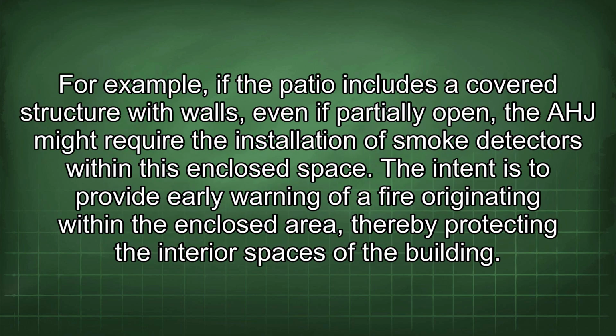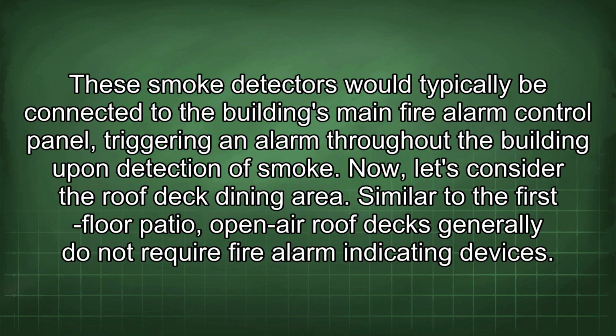For example, if the patio includes a covered structure with walls, even if partially open, the AHJ might require the installation of smoke detectors within this enclosed space. The intent is to provide early warning of a fire originating within the enclosed area, thereby protecting the interior spaces of the building. These smoke detectors would typically be connected to the building's main fire alarm control panel, triggering an alarm throughout the building upon detection of smoke. Now let's consider the roof deck dining area.